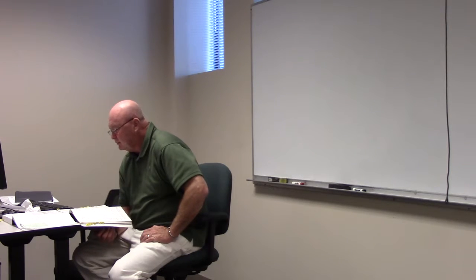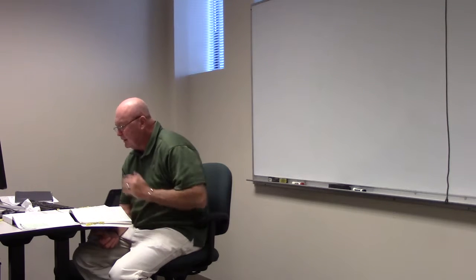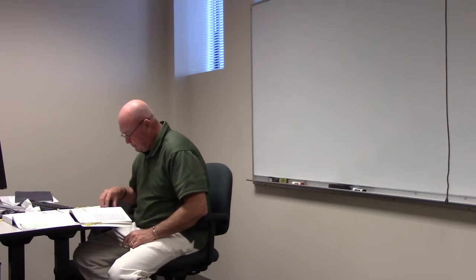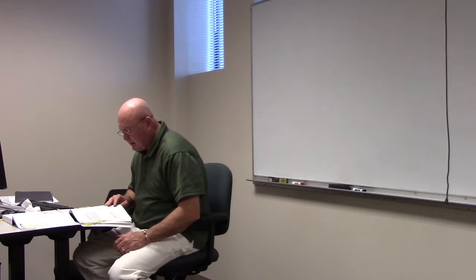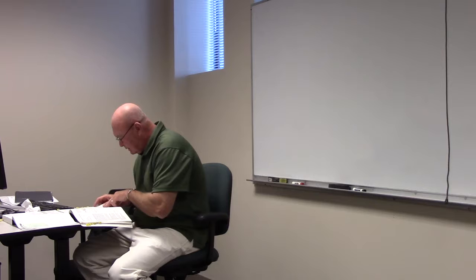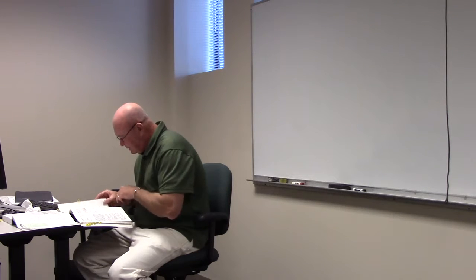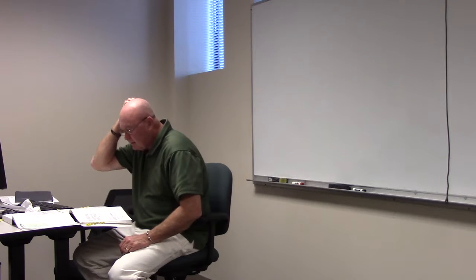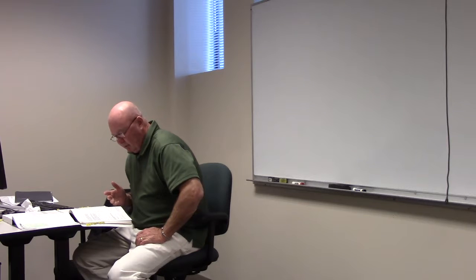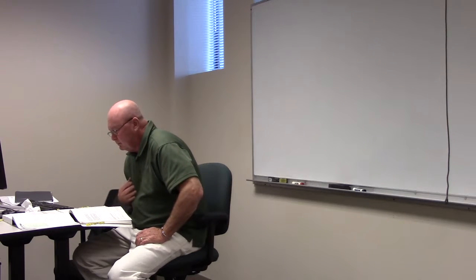All right, lighting loads, 3.1.1. Lighting loads are divided into 7 different categories. We looked there, 220.12. It's just general lighting. And we see that on our table. 220.12 lists branch circuit load, load for specific occupancies, and if you go on down, we're just talking about general lighting by occupancy, whatever it happens to be, and we see that there on our table, don't we? Our load on our lighting varies depending on what's actually in the space. Like, you don't need as much lighting for a warehouse as you would for a school, right?